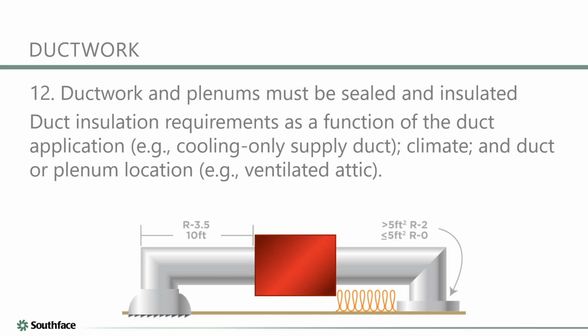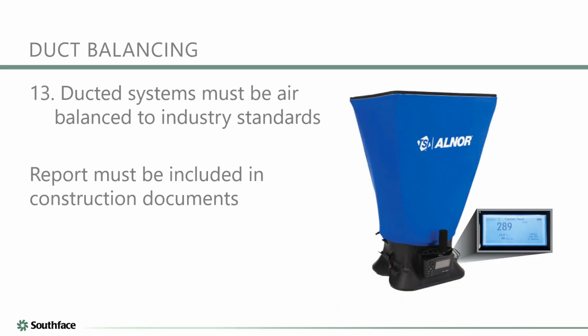Sure. Burke, you talked a little bit about air balancing there, so why don't you take us through the duct balancing requirement here? So duct systems must be tested and balanced, and it's an interesting sort of code way of speccing this. It says balanced to industry standards. We typically say that's within 10% of design flow. This is a big one, and this is another one that I think is probably often being ignored in that someone puts balancing, maybe they say we're gonna do system balancing, but does it actually happen? Does a report actually get generated and submitted? And then if it does, was the testing actually done, or did somebody just sort of go, oh yeah, I'm sure it was fine?